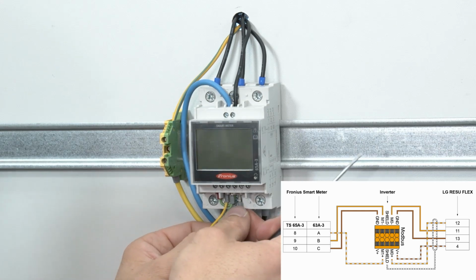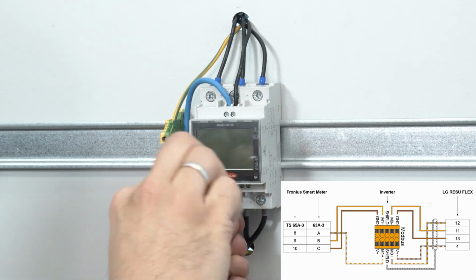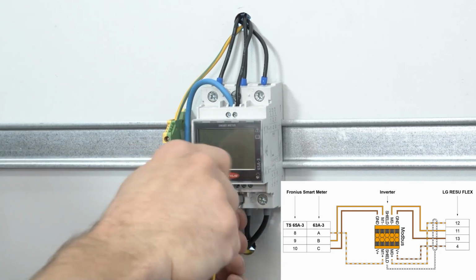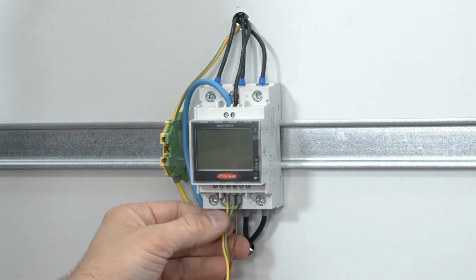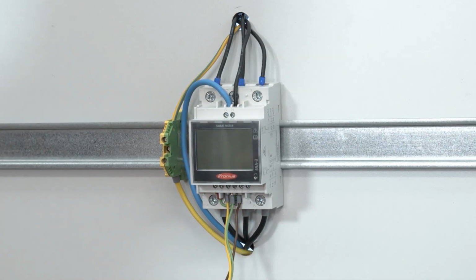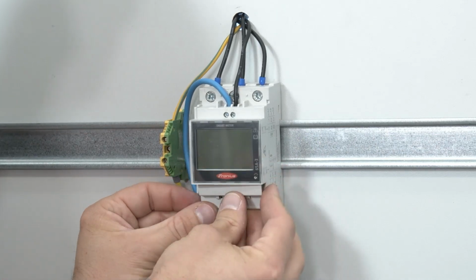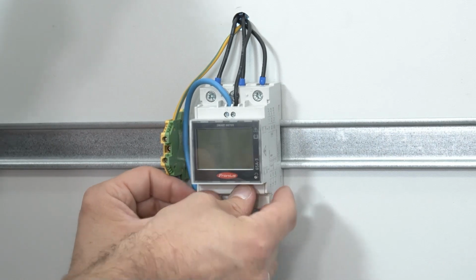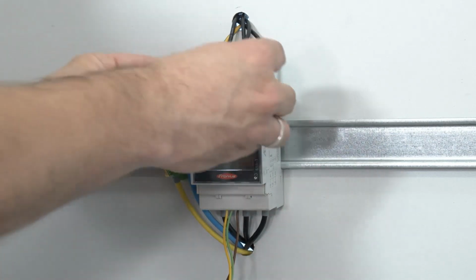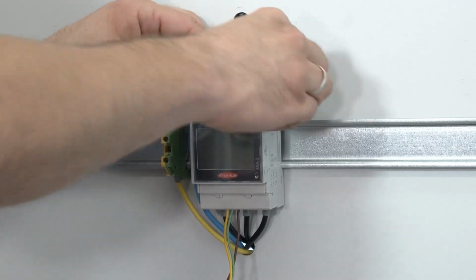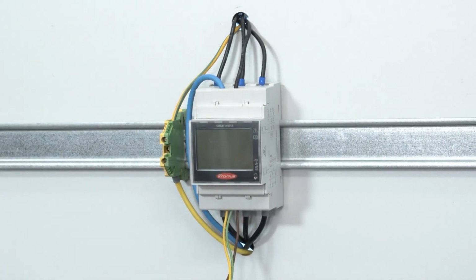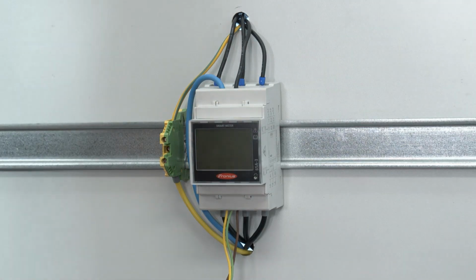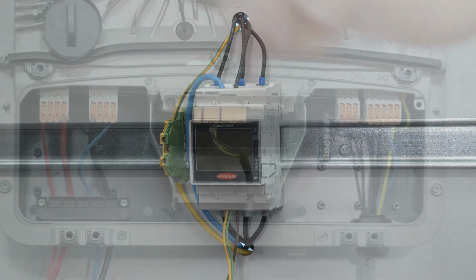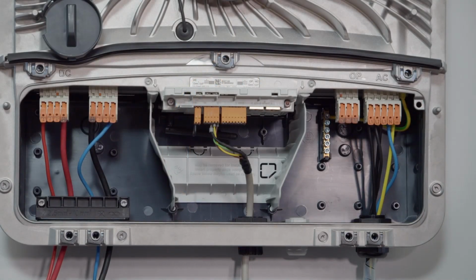And then the last contactor is contact number 10. This is then our ground contactor going to the Fronius smart meter. So as you see, whenever you have the 3 pins ready, this is then our data communication, and at the last point you can also set down our cable lugs, our little plastic covers, on the Fronius smart meter to finish the installation on the smart meter itself. After that we are going forward with the data communication from the GEN24 Plus to the LG battery, and therefore the next step is to watch the data communication to the LG battery system.